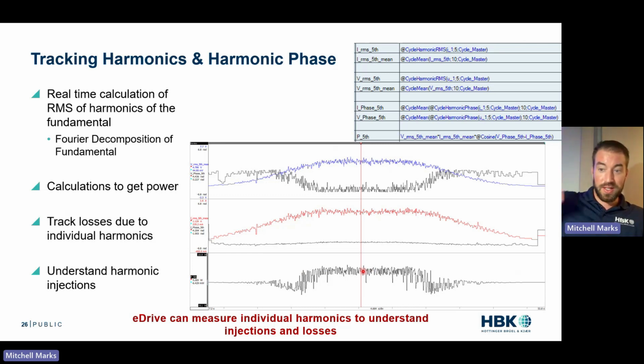You can look at your harmonics during transients. You can do all this cool stuff to analyze your harmonics, your harmonic losses through things like drive cycles. Again, we're doing this on the cycle basis. We're doing this in real time in hardware, and you can track those individual harmonics. You can track those harmonic injections all dynamically. So it's really cool. You don't have to go to MATLAB. You can do it in your acquisition equipment. So eDrive can measure the harmonics and understand those injections and losses without going to MATLAB, without getting a scope. You can do this all in your power analyzer, one piece of equipment.